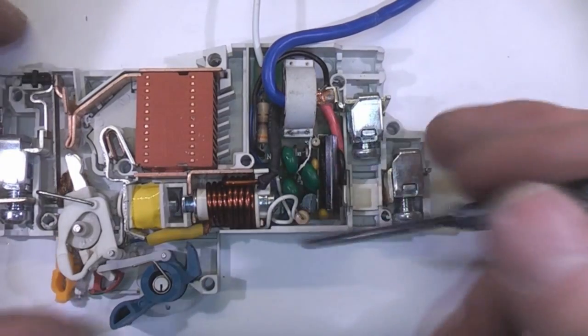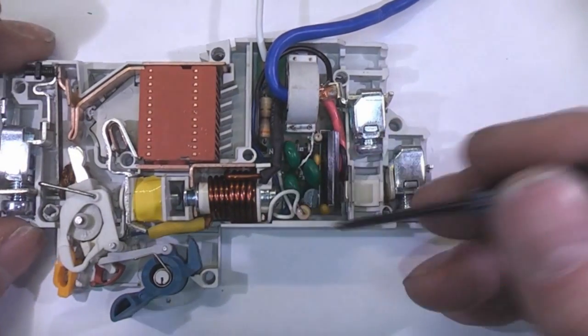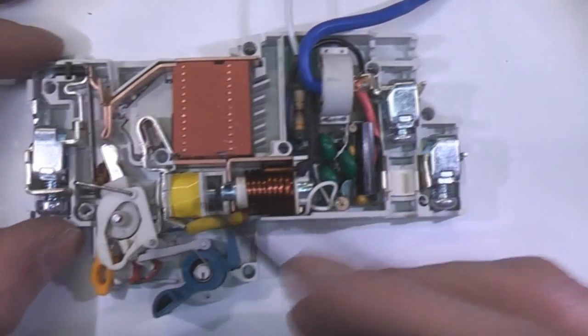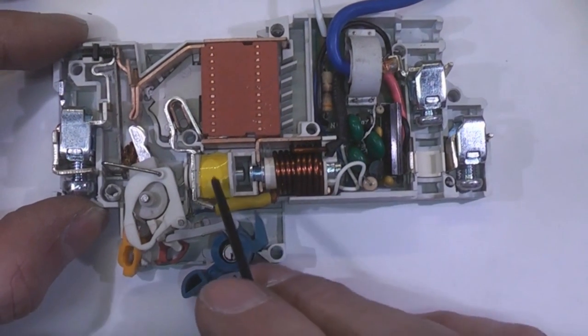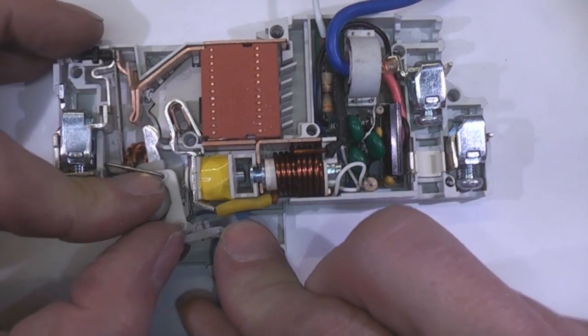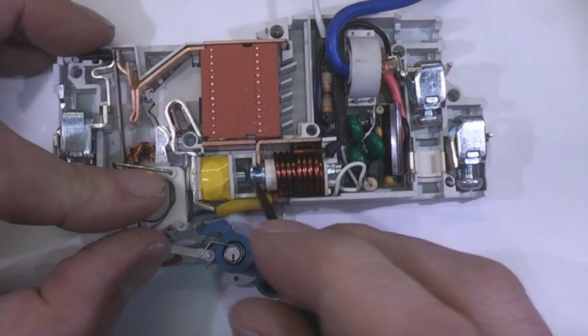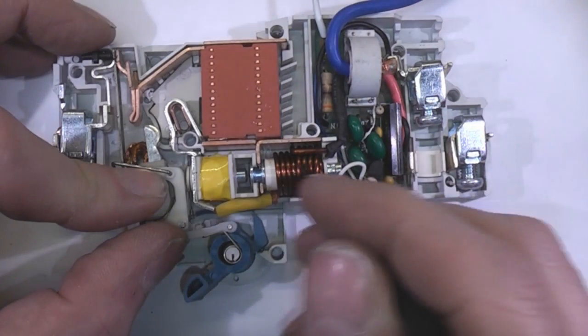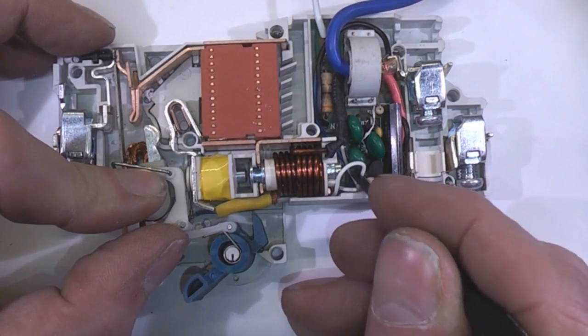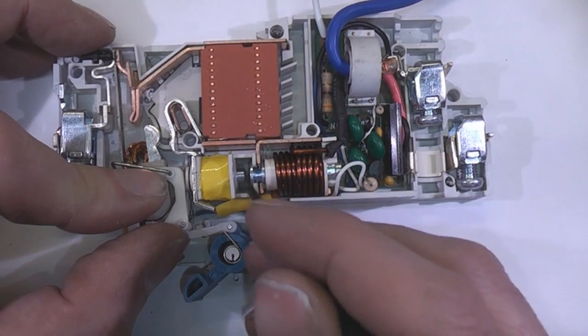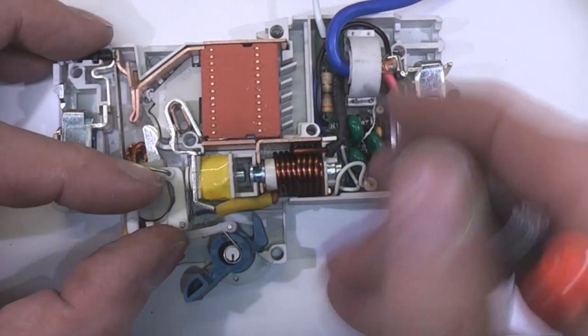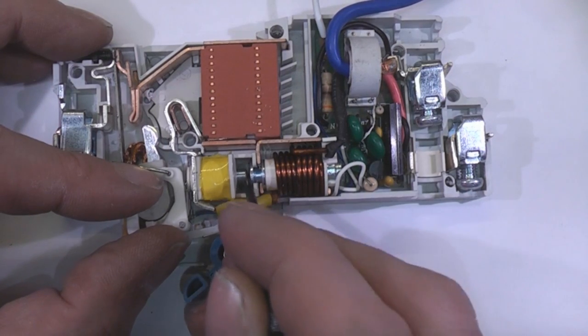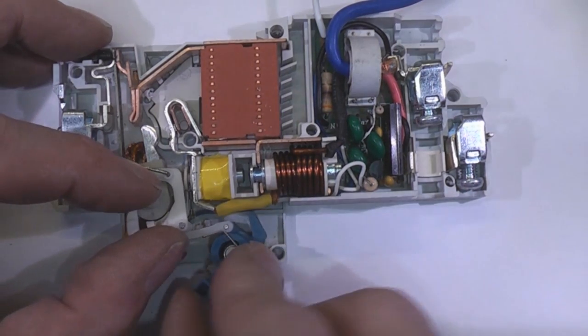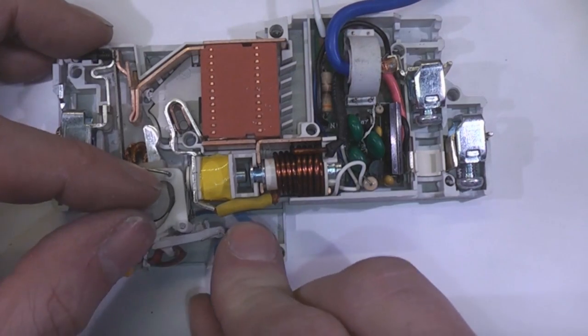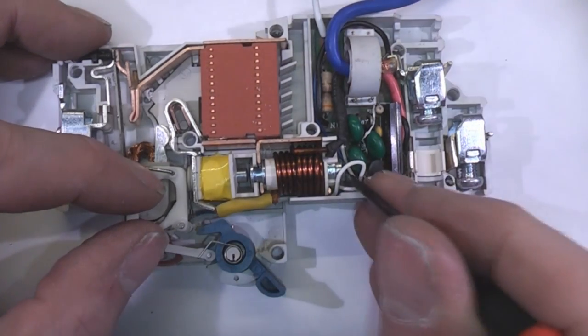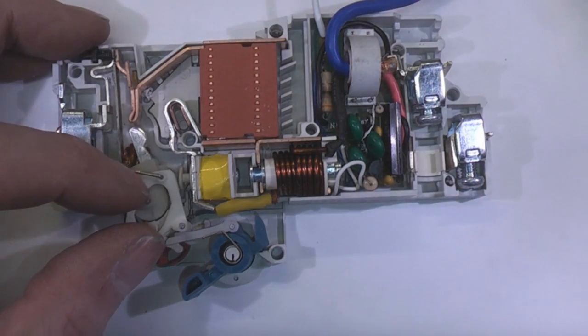So this one, once I opened it up, actually seemed to start working again, so I don't know if it was mechanically jammed or something, but the electronics do still seem to work. And the RCD trip is actually this coil here. So basically we've got a quite complicated piece of mechanics. This is the magnetic part of the overcurrent protection. If you get too much current, this solenoid pushes this little lever through, and if the RCD trips, this solenoid operates and pushes this through and then trips it. So if we just turn it on, this pushes through, that just trips it out.